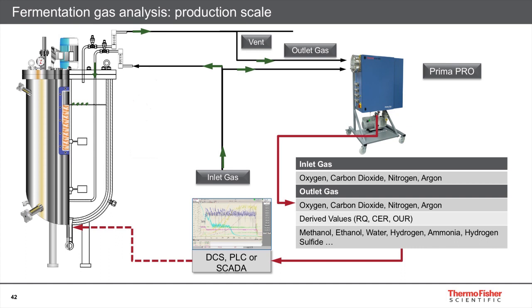Principally, air gases are monitored — oxygen, CO2, nitrogen, and argon — but it is a fully functional mass spectrometer capable of monitoring many gas species in a fermenter headspace, including methanol, ethanol, hydrogen, ammonia, and H2S. As a PAT tool, it integrates into a workflow with a fermenter and bioreactor controller. Data from the mass spectrometer is routinely fed to a DCS or SCADA system, which can then control feed rates, sparge gas rates, and impeller speeds.